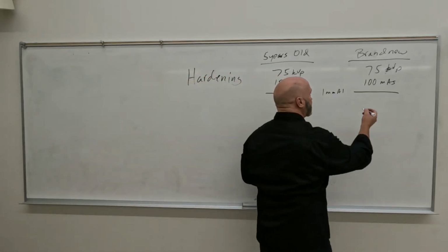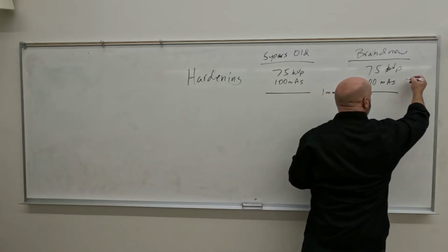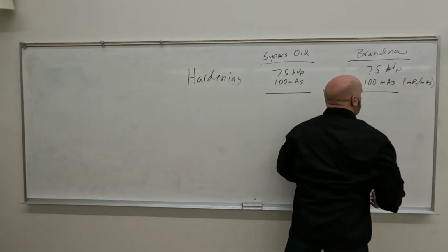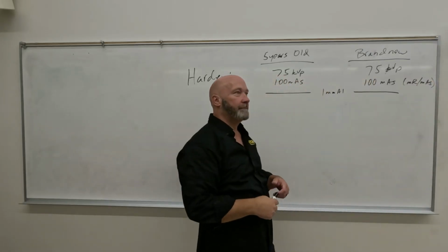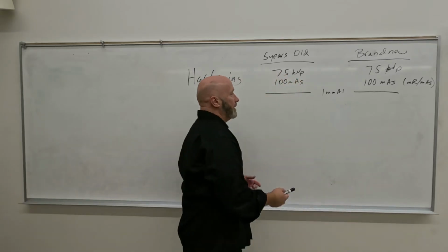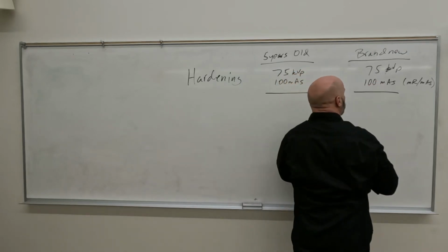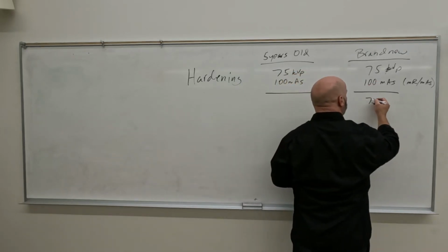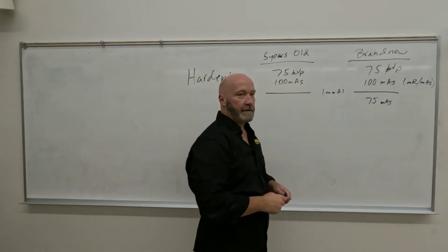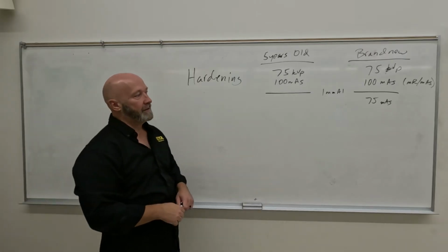Whenever they're doing the test, they're actually measuring the mR per mAs, milliroentgens per mAs, or millisieverts per mAs. So you make an exposure, and it cuts this from 100 to 75.